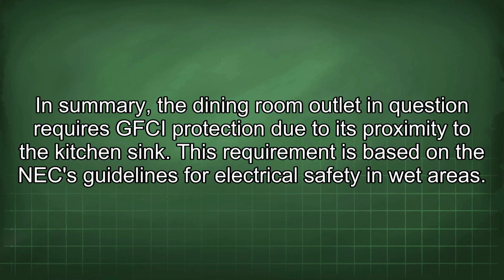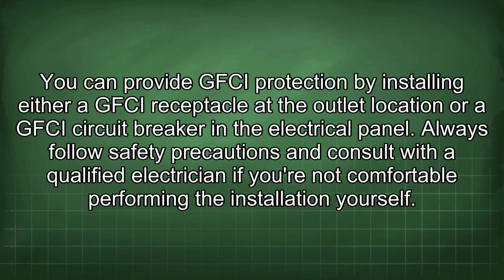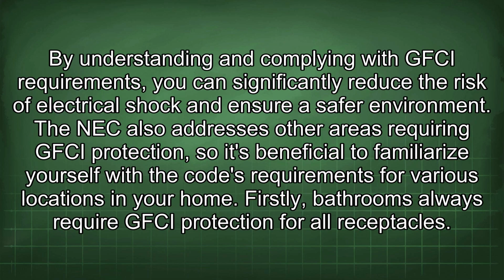In summary, the dining room outlet in question requires GFCI protection due to its proximity to the kitchen sink. This requirement is based on the NEC guidelines for electrical safety in wet areas. You can provide GFCI protection by installing either a GFCI receptacle at the outlet location or a GFCI circuit breaker in the electrical panel. Always follow safety precautions and consult with a qualified electrician if you're not comfortable performing the installation yourself. By understanding and complying with GFCI requirements, you can significantly reduce the risk of electrical shock and ensure a safer environment. The NEC also addresses other areas requiring GFCI protection, so it's beneficial to familiarize yourself with the code's requirements for various locations in your home.